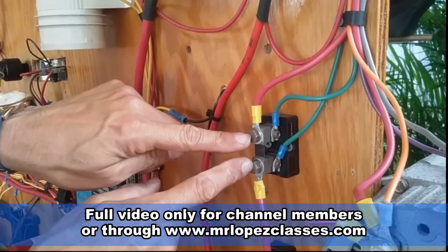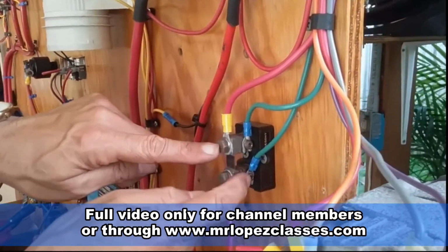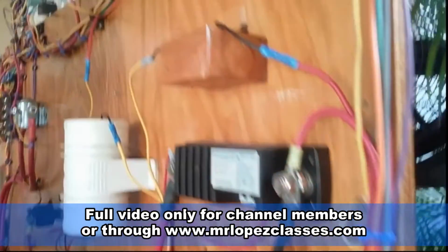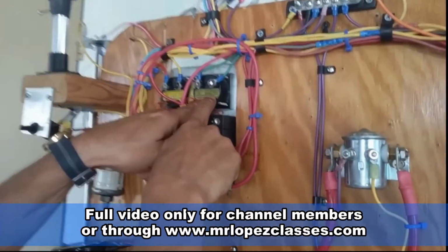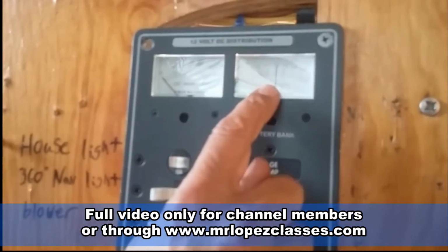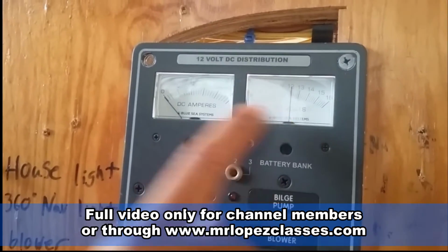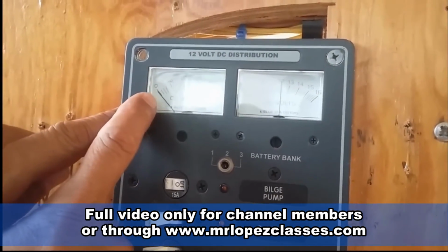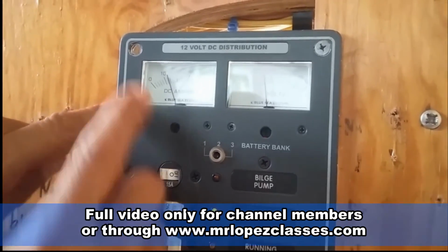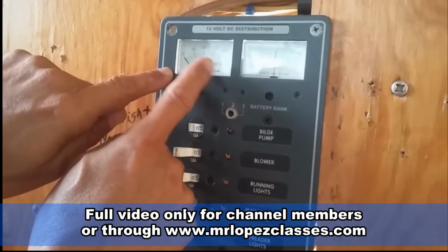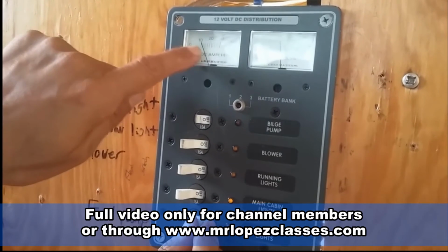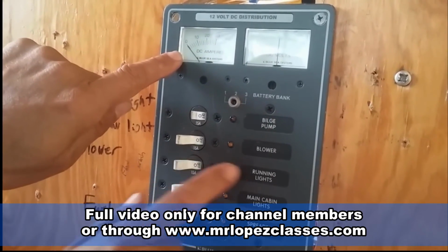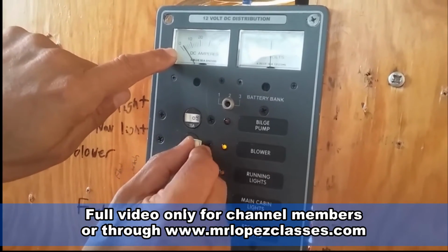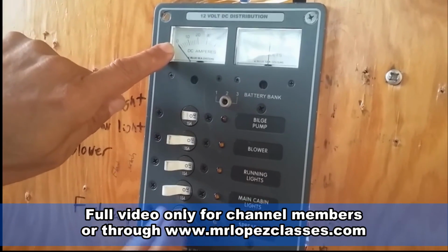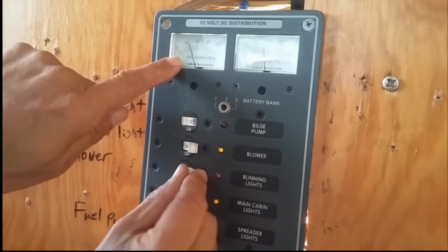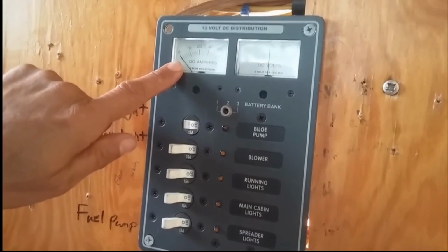On the side of the shunt, there are two small connections where I connect both small green cables, and those small green cables enter here into the ammeter, and this is the connection for the ammeter. The voltmeter shows 12 volts, 12 point something. The ammeter, nothing. Let me apply load and you see that the needle goes up. You see the consumption in amps on the DC ammeter, 10 amps, that's the consumption of the fuel pump, you remember? And the other one, the blower, the consumption is 2.4. 2.4 plus 10, 12.4, plus the lights, that's the consumption of the panel right now, around 15 amps.